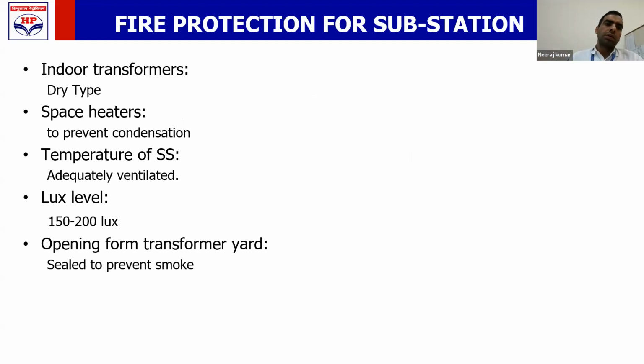If your substation has an indoor transformer, mostly transformers are placed outside the substation, but in case the transformer is inside the substation, then it has to be dry type. Even though it is not a mandatory requirement, you can still keep an oil-filled transformer inside the substation, but then the firefighting requirement and oil containment requirement will become very difficult to manage, especially for medium or big size transformers. For a very small transformer of say 500 liters, you may be able to meet the requirement of firefighting and oil containment. But in general, it is always better to have a dry type transformer if it is to be installed inside the substation.